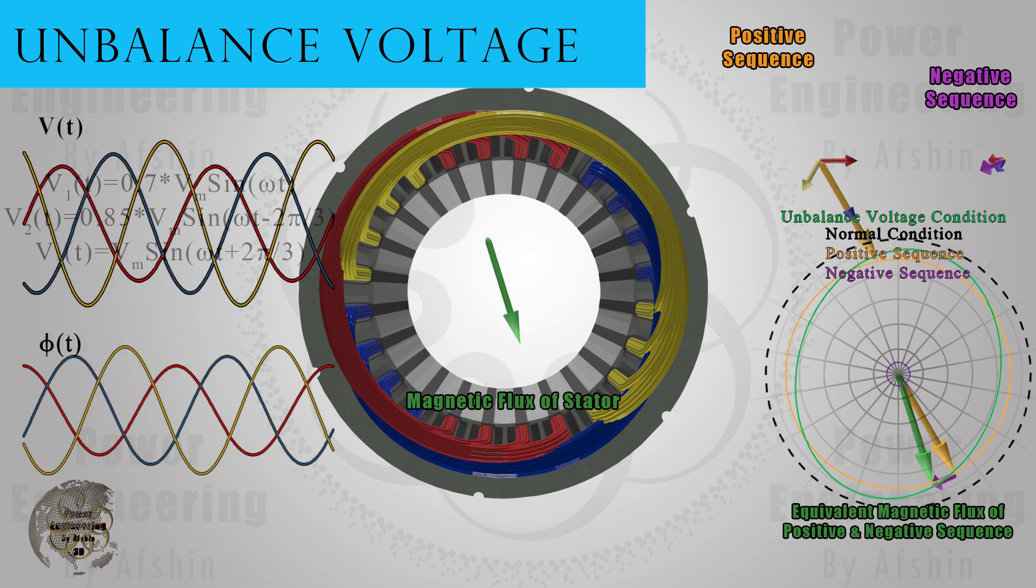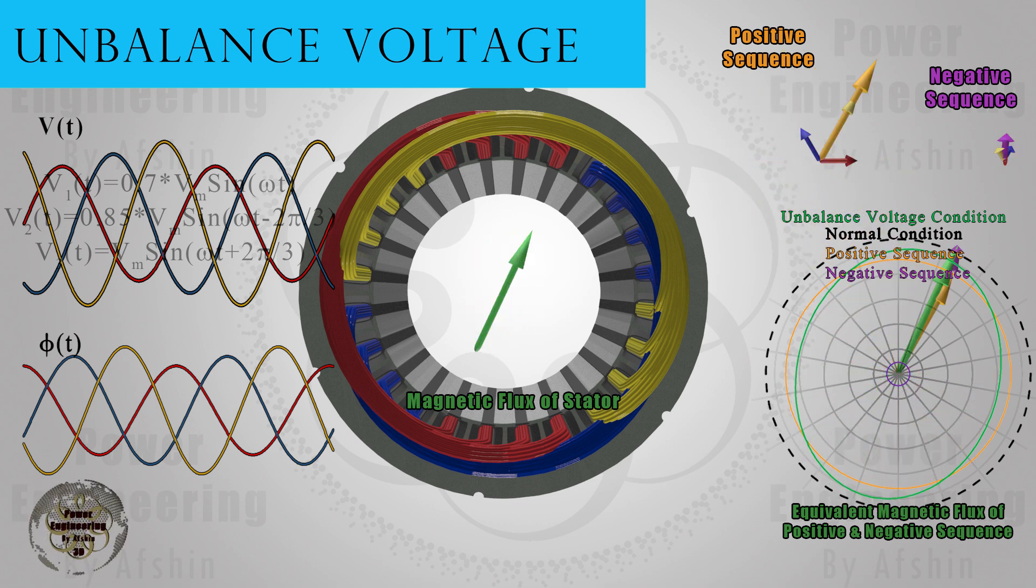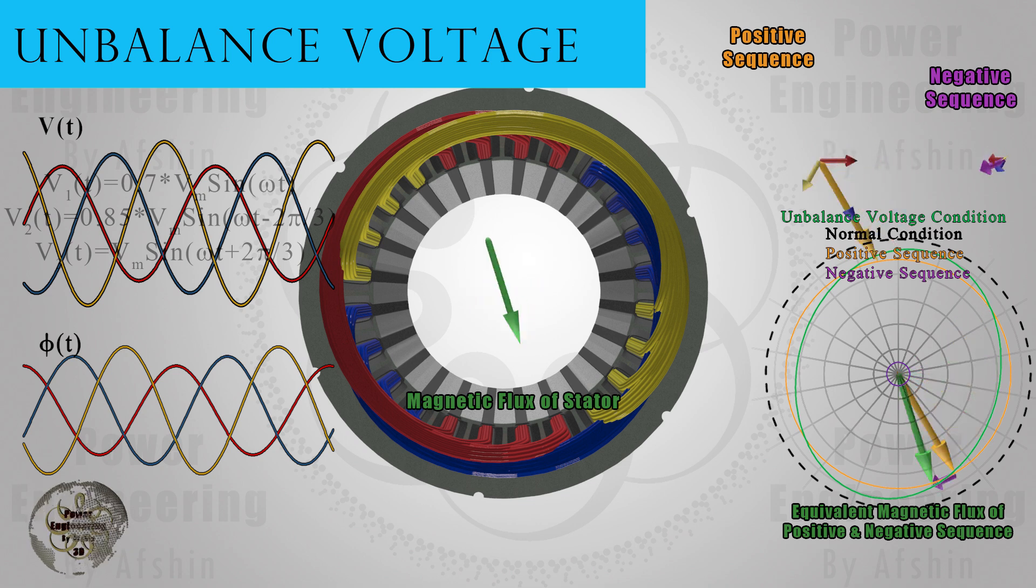In these conditions, the rotating field has both positive and negative sequences. However, there is also zero sequence. But since the zero sequence does not contribute to the creation of the rotating field, we disregard it. The presence of the zero sequence leads to heat generation, losses, and saturation.